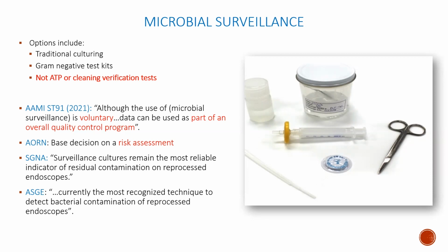Options for surveillance testing include traditional culturing and gram-negative testing. This is not cleaning verification, nor is it ATP testing at this point. Surveillance testing looks for evidence of microbial contamination. This slide shows current guideline reference to microbial surveillance. Significant to note is that FDA-mandated surveillance testing showed that 5.4% of cultured scopes were positive for organisms of concern.